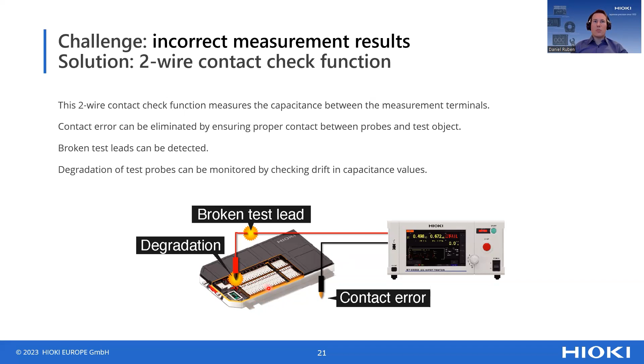Another important point why a 2-wire contact check function is superior to the 4-wire method: it's not only that you can save 2 wires, but also the points to probe on are becoming smaller and smaller. If you have only 2 probing points to set on this installation point, or sorry, enclosure, or on the pole, it's easier than with 4 points.